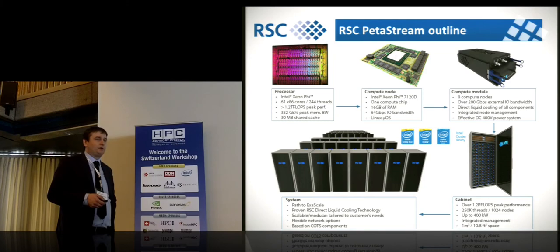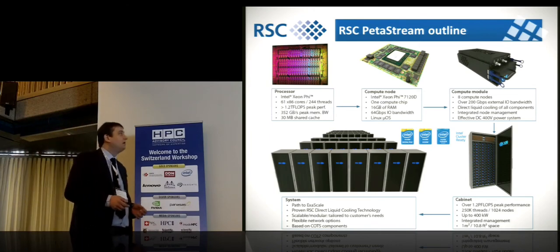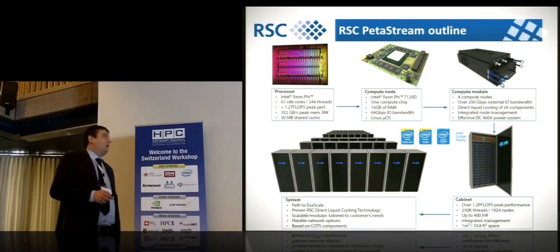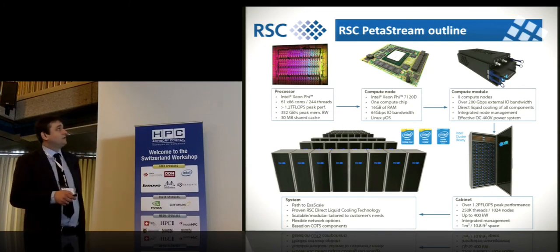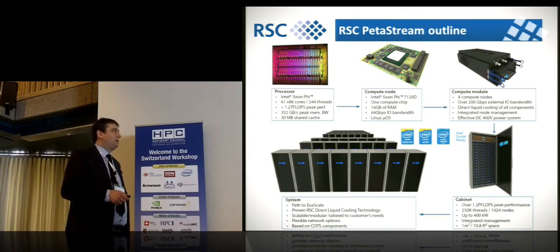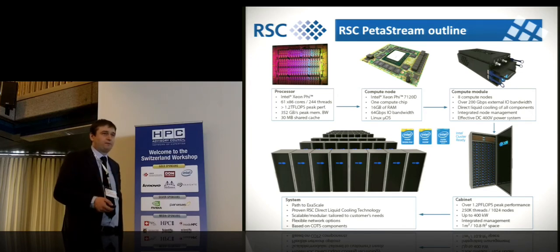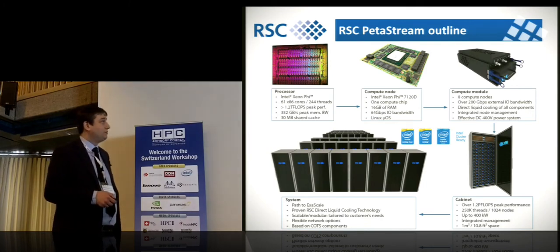We had to innovate in terms of the power distribution system, because at that scale and that compute power density, we were not able to rely on third party power supplies. Here is that compact module, about 50 centimeters in size. It dissipates about 2 kilowatts of power. If we would use standard components, half of the module would be spent just on the power supply. So we designed an effective power supply using innovative direct current 400 volt electric distribution.